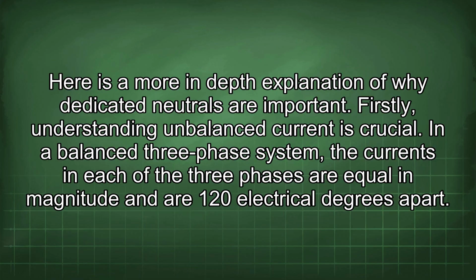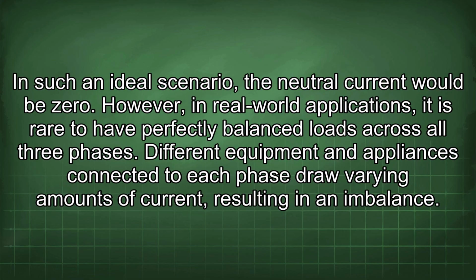Here is a more in-depth explanation of why dedicated neutrals are important. Firstly, understanding unbalanced current is crucial. In a balanced three-phase system, the currents in each of the three phases are equal in magnitude and are 120 electrical degrees apart. In such an ideal scenario, the neutral current would be zero.